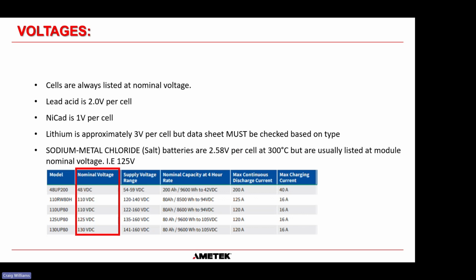And if we go back to the start, voltages. Cells are always listed at nominal voltage. Okay, so for a lead acid, it's 2 volts per cell. For a NiCad, it's 1 volt per cell. For lithium, it's approximately 3 volts per cell, but you must check the datasheet based on the type, because there are many different technologies that have different nominal voltages. And then for the salt batteries, they're usually 2.58 volts per cell at 300 degrees Celsius, but are usually listed at module nominal voltage.